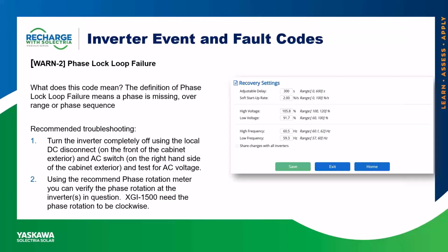In that case, it is more of a byproduct of the current situation, as there just is no AC present at the inverter. Now, as for recommended troubleshooting, the first thing you would want to do is turn the inverter completely off using the local DC disconnect found on the front of the cabinet exterior and the AC switch found on the right-hand side of the cabinet exterior, and test for AC voltage. The par value for AC voltage will either be 480 or 600 volts phase to phase and 277 or 347 phase to ground, depending on the inverter class you have installed. Now, that being said, these inverters have programmable AC voltage ranges that it will adhere to that can go above or below the par value.